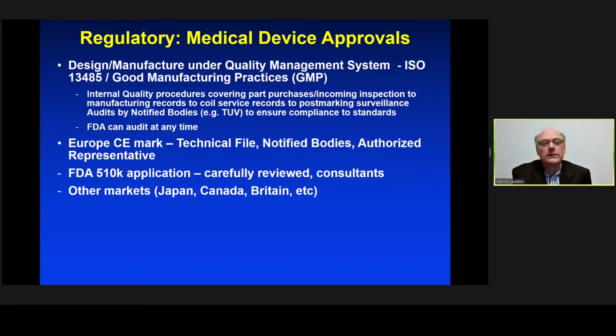An MRI coil is a medical device, and you need to look at the regulatory side of the coil, particularly medical device approvals. All of your design and manufacturing needs to take place under a quality management system, ISO 13485, GMP, or equivalent. This is a very large set of internal quality procedures, which covers many company operations, everything from part purchases to post-marketing surveillance. The system will be audited by external auditors, such as notified bodies, to ensure you have compliance to these standards. Of course, the FDA, if you're building for the US market, can come in at any time.